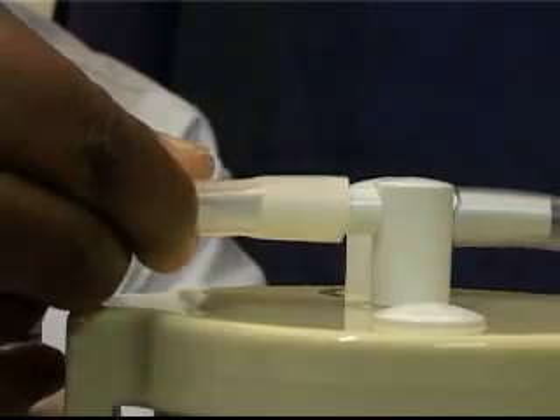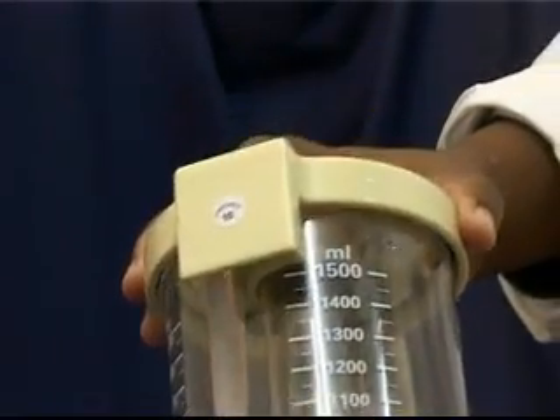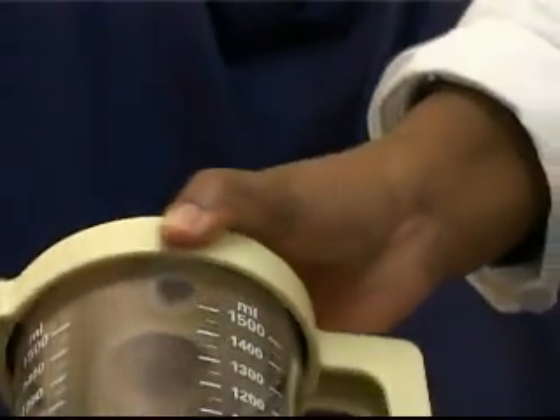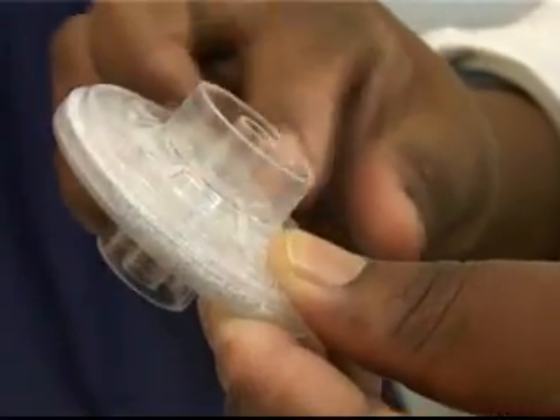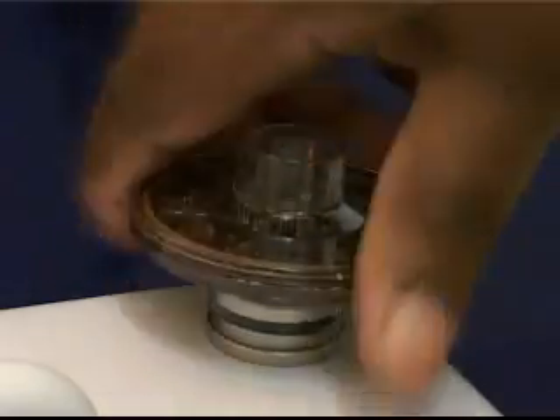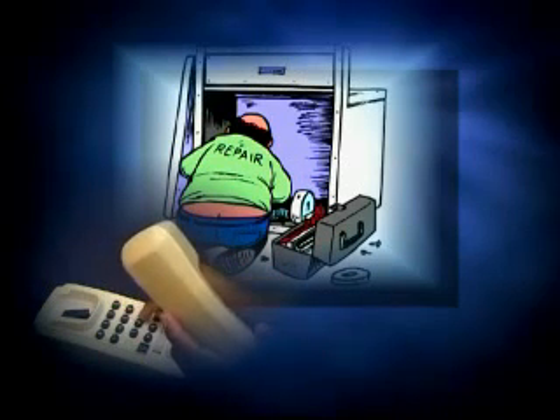and check that all tubing is properly connected. Ensure that the bottle is correctly screwed into the cap. Check the filter assembly for cracks and splits. Make sure that the filter is clean and replace it if necessary. Any problems which cannot be rectified easily must be reported so a technician can attend to it.